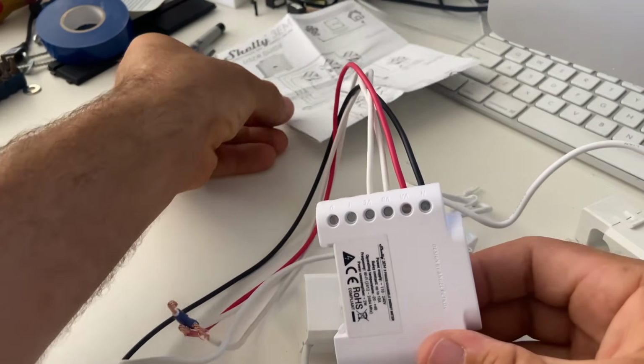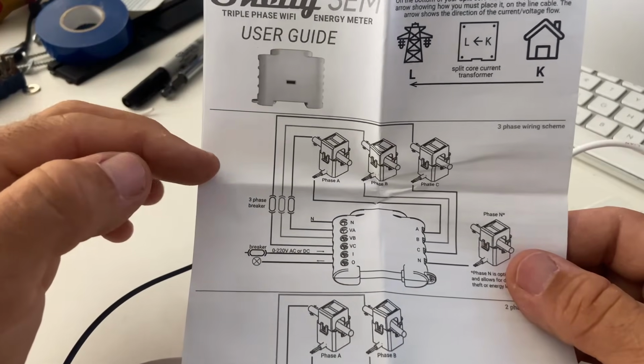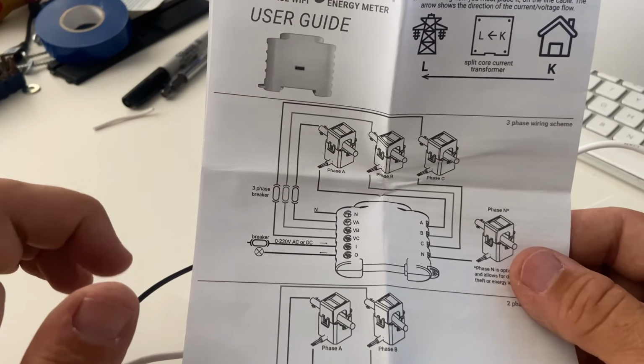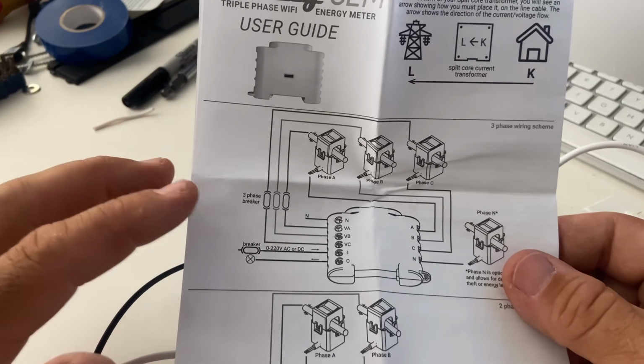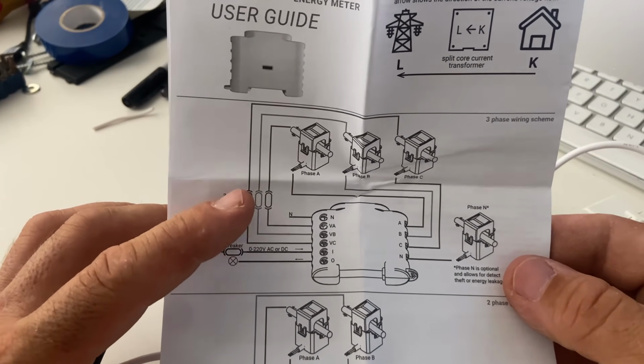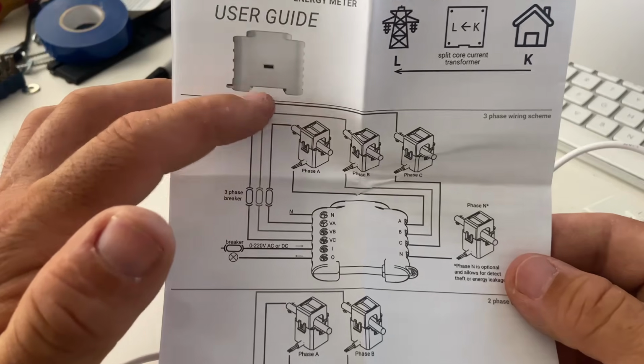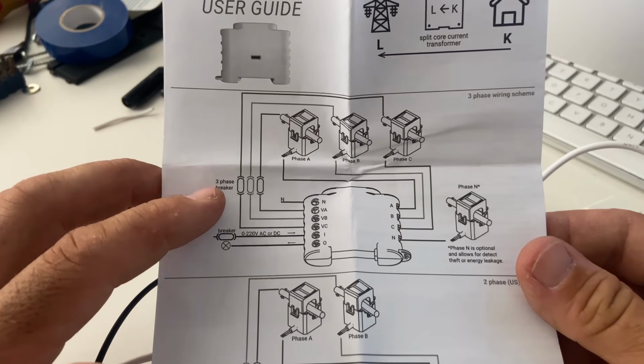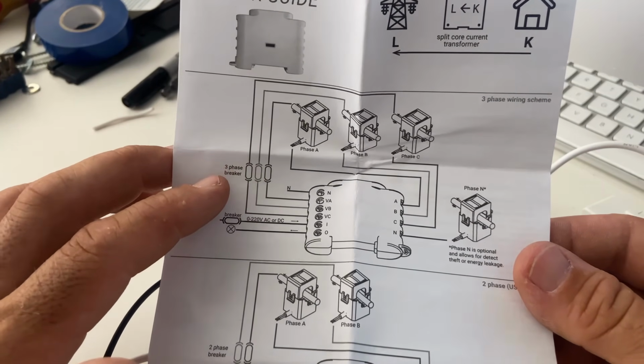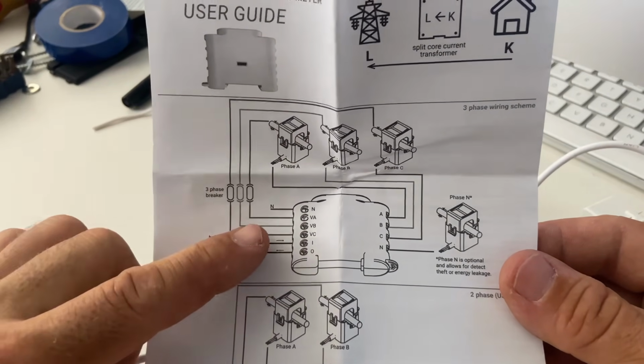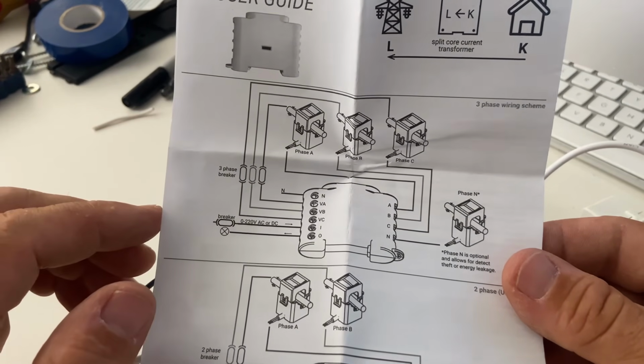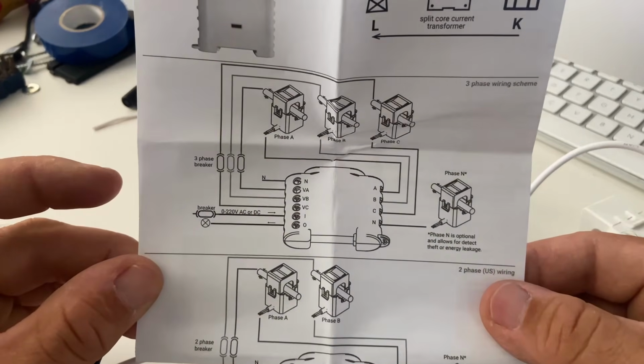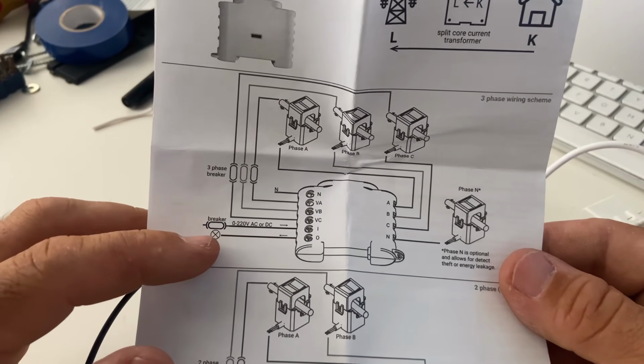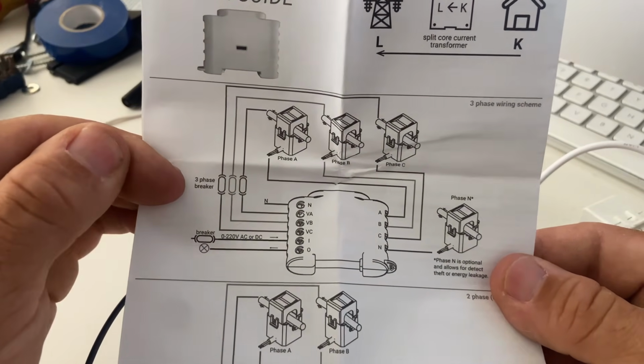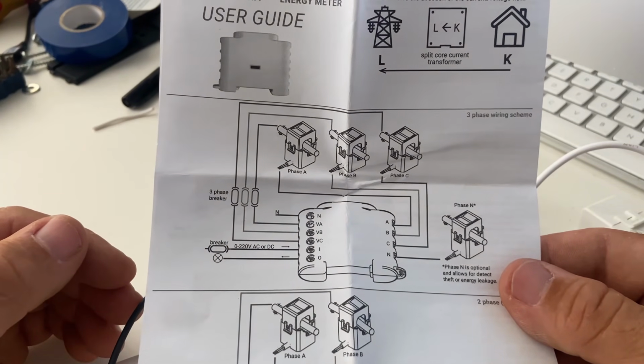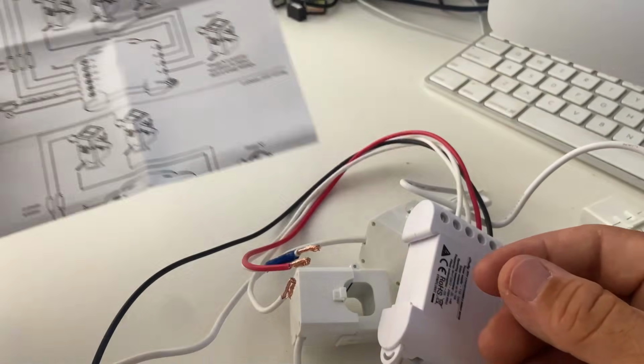It is recommended that you connect it via a 3-phase circuit breaker, which I have. I've got a 10 amp one because you can get smaller ones, but that's the smallest I happen to have. That goes to the load side of my main switch. I guess you could use some inline ceramic fuses as well, bearing in mind that this draws only a very, very small amount of current, like in the 0.1 amps range, so it doesn't use much at all. But if you do use a 3-phase circuit breaker, bear in mind that's going to take up more space once again - it's going to take up 3 modules.